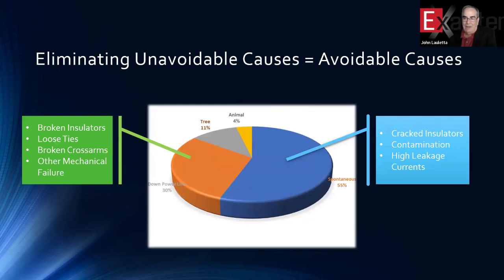So what are the avoidable causes of pole fires? Well, broken insulators, loose ties, broken crossarms, mechanical failures on the pole itself. And then there's the spontaneous combustion events, which are generally associated with cracked insulators, contaminated insulators, and high leakage currents that result from those events. So we're going to focus in on those 2 areas today because these are areas that you could do something about. You could avoid all of these if you use predictive maintenance strategies within your utility to find problems and eliminate them from the pole or from the line or from the circuit prior to collateral damage occurring, like a pole fire, and then the further collateral damage that results from that pole fire.